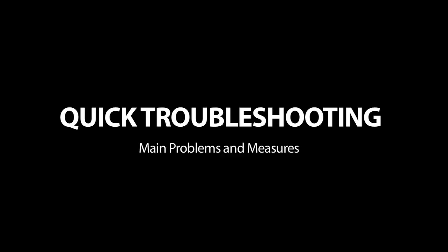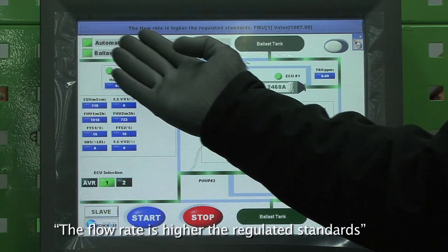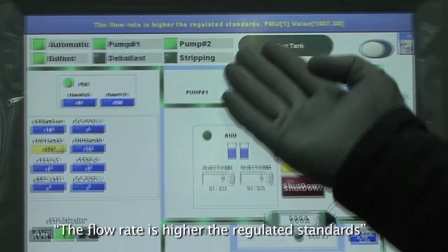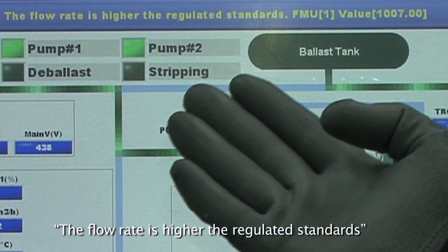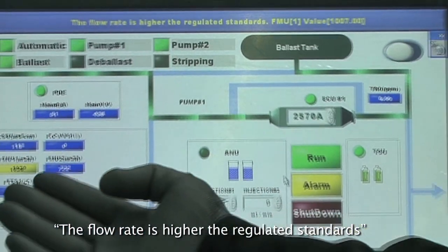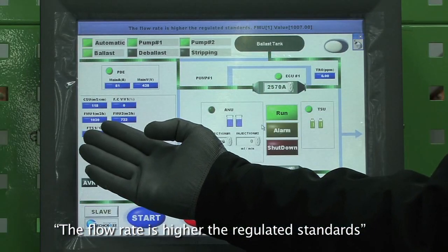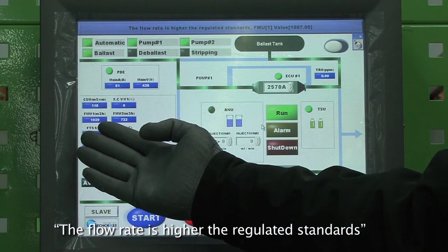Quick troubleshooting. 1. Main problems and measures. Problem. ECS shuts down 1 minute after alarm message. The message "flow rate is higher than the regulated standard" appears. Reason. When flow rate is above the normal range.